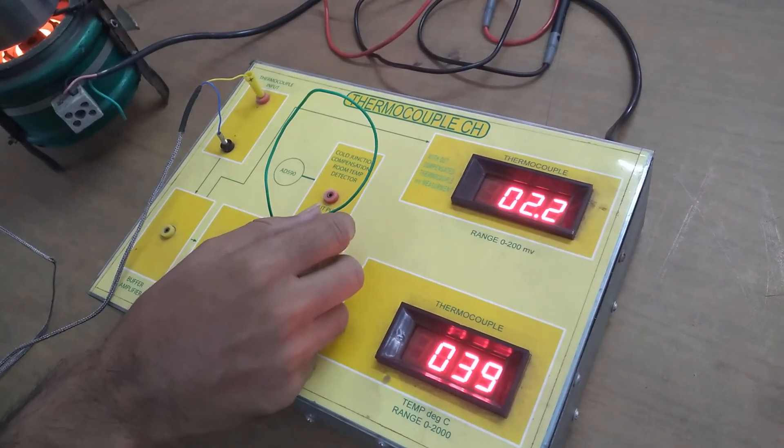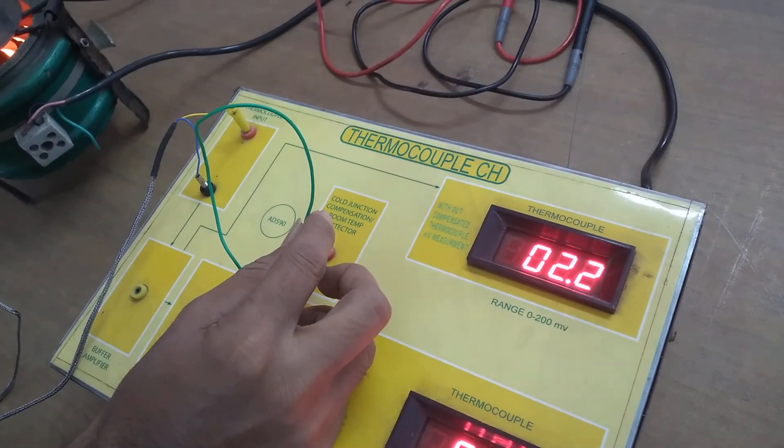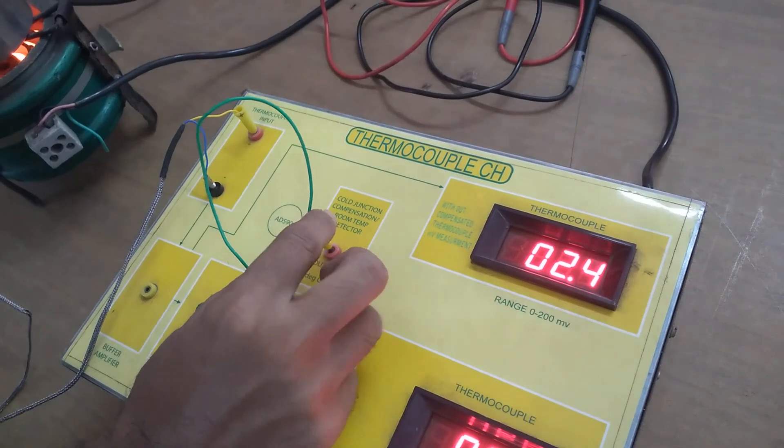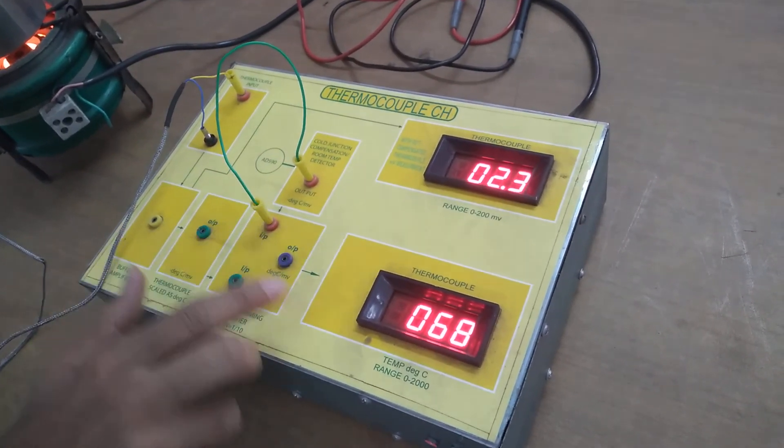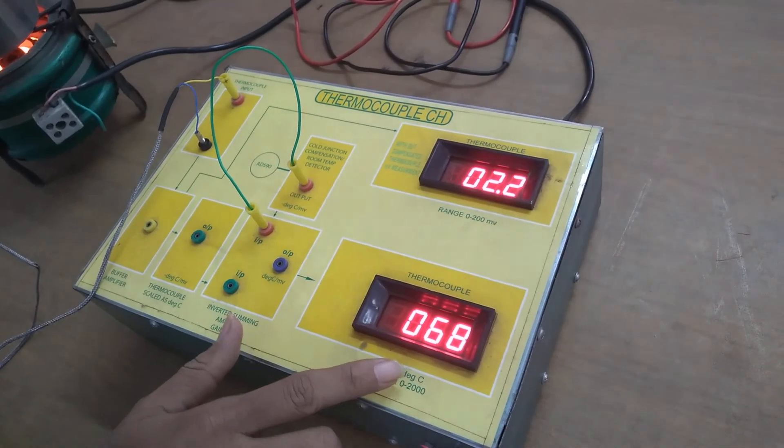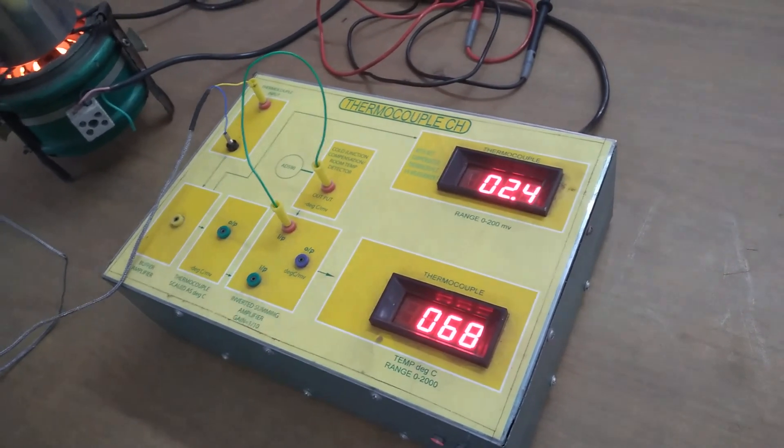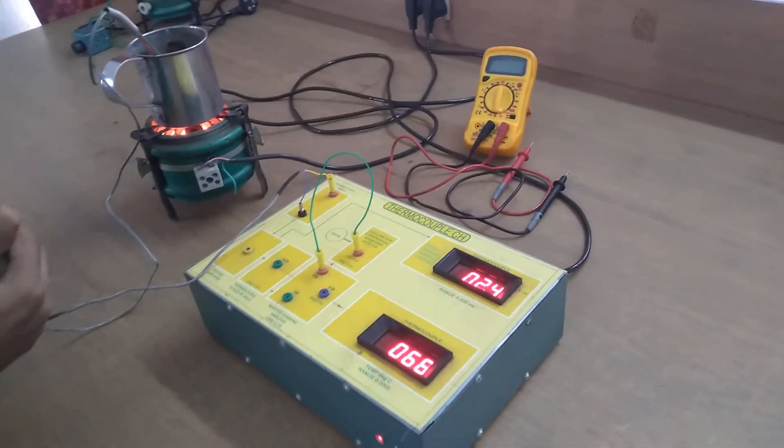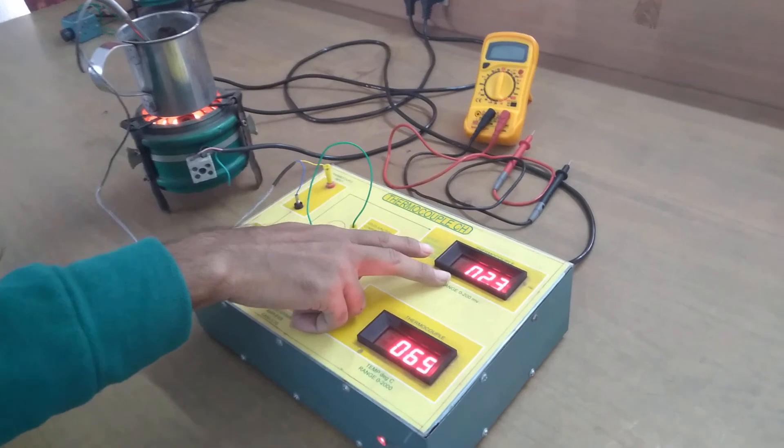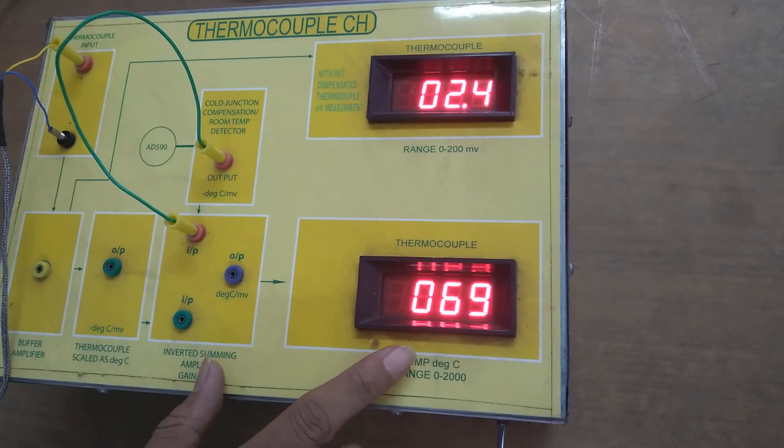But if we go for cold junction compensation, which is how a thermocouple conditioning circuit should be done, what we find is that the actual process temperature was 68 degree centigrade. Now as temperature keeps on increasing you will find that this millivolt will also increase and correspondingly this temperature display will keep on increasing.